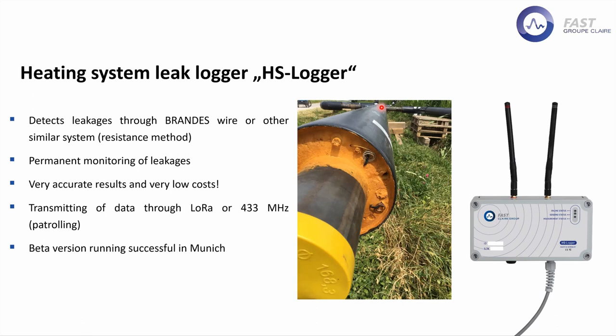We also have a project in Dubai for Emicool, where we have similar problems. In heating systems, you have condensers, pumps running all the time, and heat exchangers, which create a lot of noise. So you can't use our noise loggers and other technologies for detecting leaks in heating systems. But with the heating system pipes we install here in Germany, mainly with Brandes wires inside, it's still very easy to detect leaks.